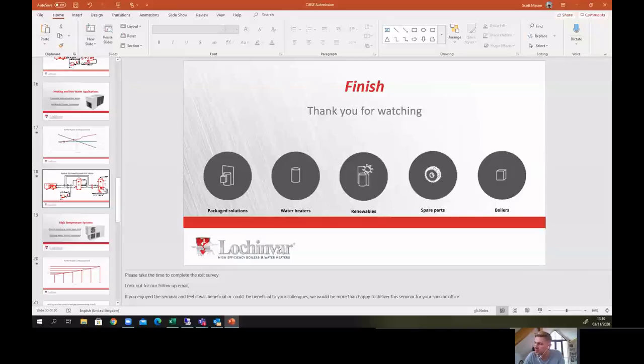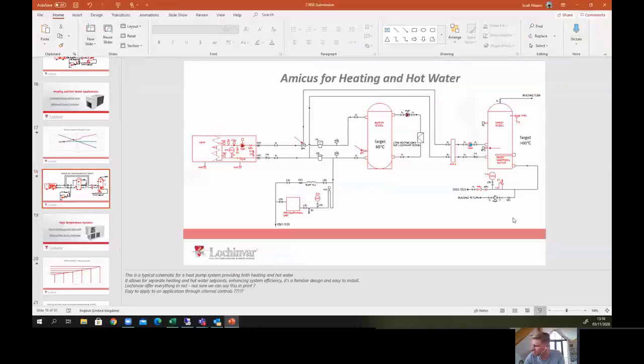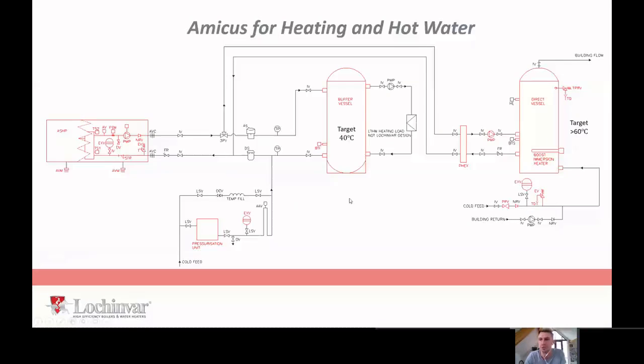No, so what you would have to do, so the maximum absorption temperature for most water source heat pumps, I'll probably say all, to be honest, but I don't make everyone's, it's going to be about 35 to 40 degrees centigrade, and that's because there's only so much work you can do between the primary and secondary, and it creates some temperature issues as well, because the water source can accept temperatures down to like -5. So your maximum incoming is going to be about 35 degrees centigrade realistically.